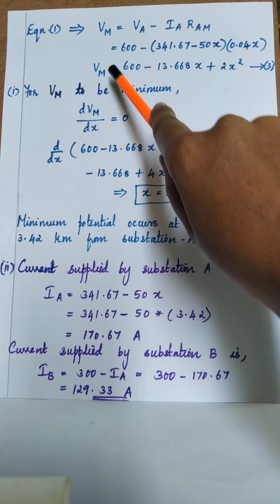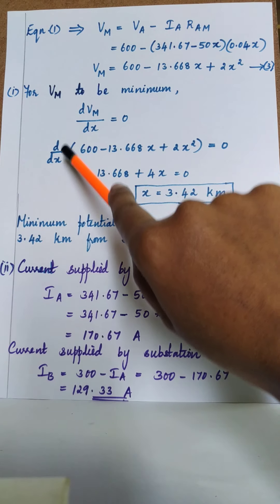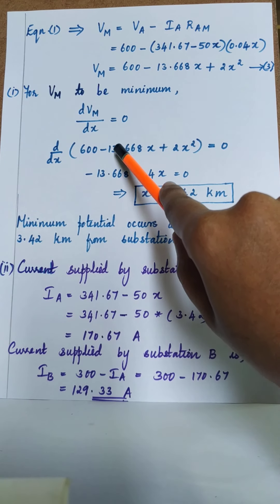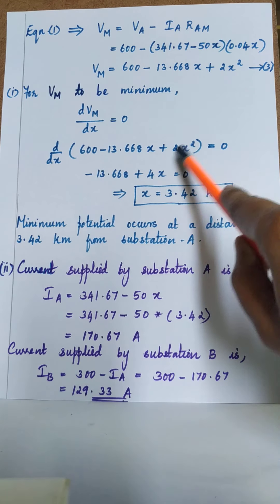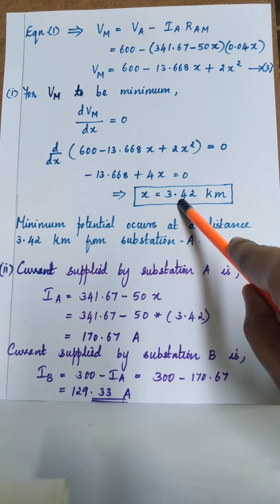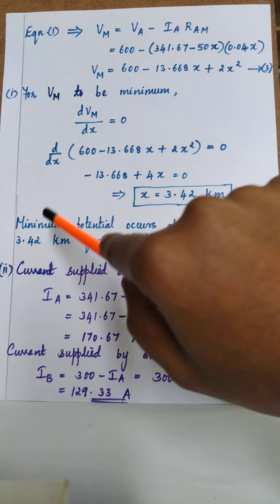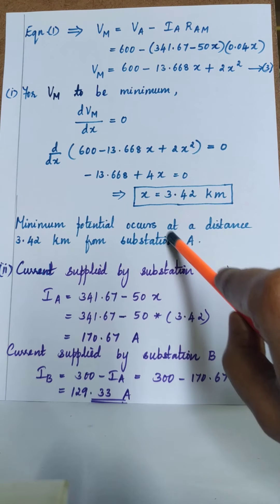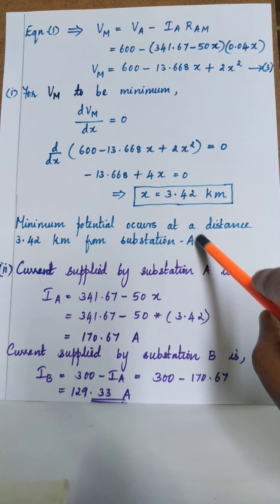Setting dVm/dx = 0: differentiating 600 minus 13.668x plus 2x² with respect to x gives minus 13.668 plus 4x = 0. Solving, x = 3.42 kilometers. So the answer for part one is that the minimum potential occurs at a distance of 3.42 kilometers from substation A.